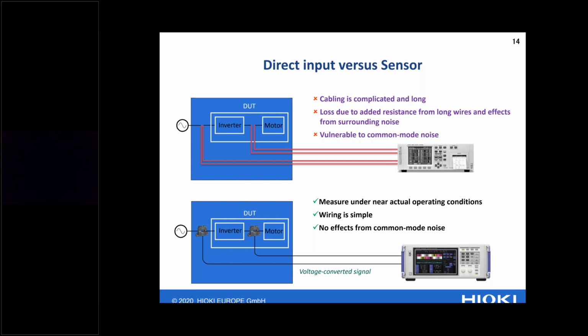The direct connection goes via a shunt, which should be included. Most people are not changing the shunt every year to compensate for what happens because of heating inside the power analyzer.